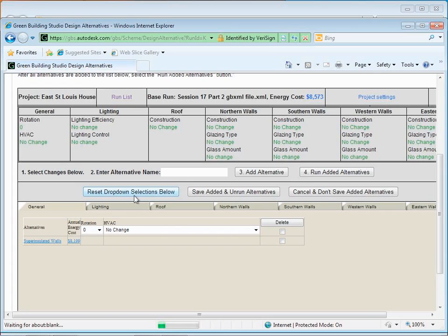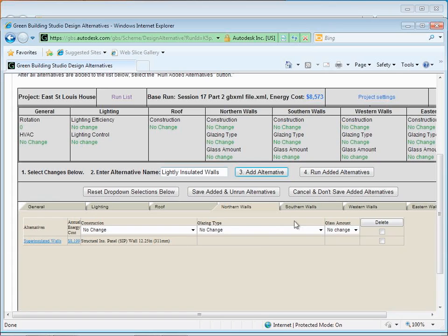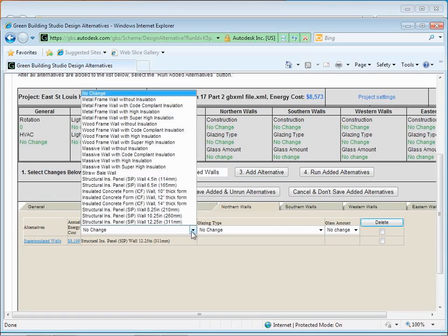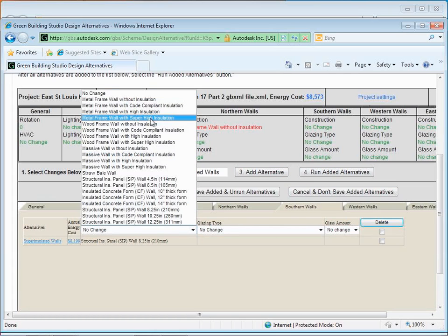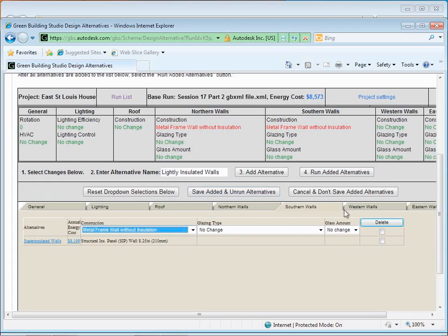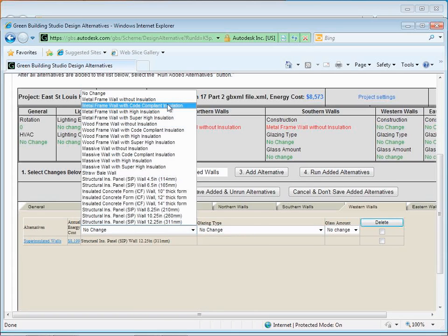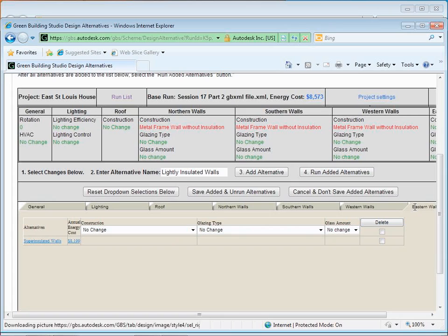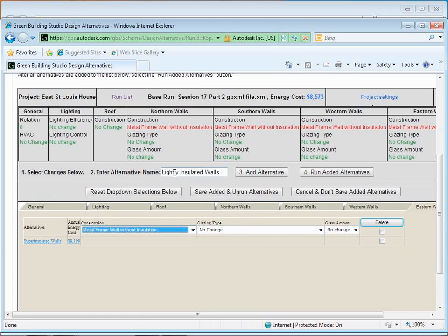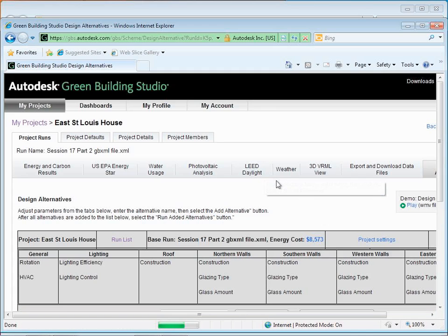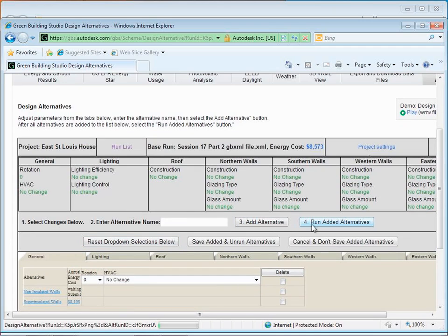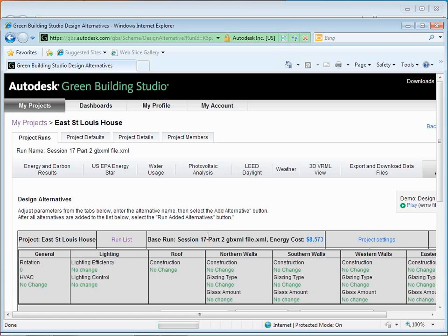So how design alternatives work is you can really change any of the different variables you're seeing here. We can change the wall construction, the glazing percentage or the glazing type. We can change any of those different things. By changing variables down here, we add it as a run and say run it. Then we get a comparison. For example, if we wanted to change the walls, let me call those like non-insulated walls or lightly insulated walls. And for that, I'm going to say that I'm going to change it to like a metal frame without insulation. That would be sort of interesting as a baseline just to see how big the difference is. So what I'm doing is just choosing the different alternatives. Notice as I'm choosing the alternatives, the change is showing up in red up here. That's how you can keep track of what it is that you changed in this alternative.